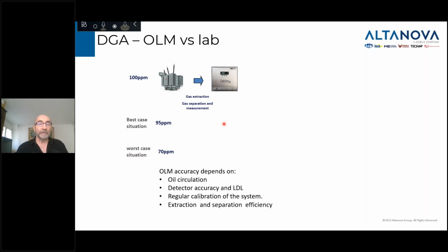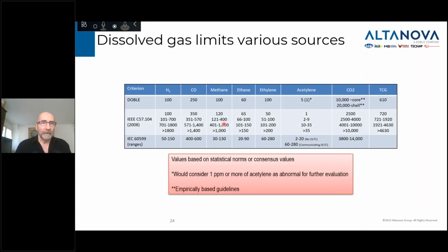Again, the detector accuracy and the low detection limit have a major impact on your measurement, mostly if you also cannot regularly calibrate the system. Again, it's an electromechanical system that for sure will lose accuracy over time. So regular calibration is absolutely critical in those kinds of systems if you want the best diagnostic. And also, what kind of extraction and separation efficiency do you have? Each type of extraction system has a different efficiency, and that will also have an impact on how you're measuring it. So now let's look at what kinds of diagnostics we're using.